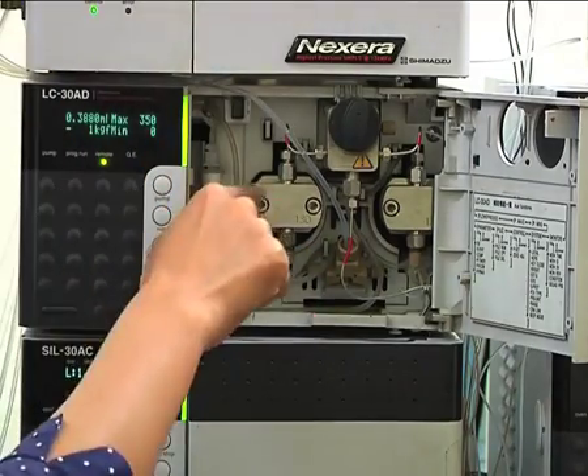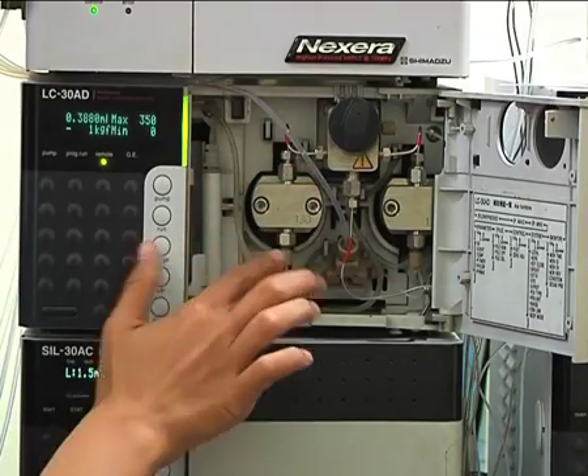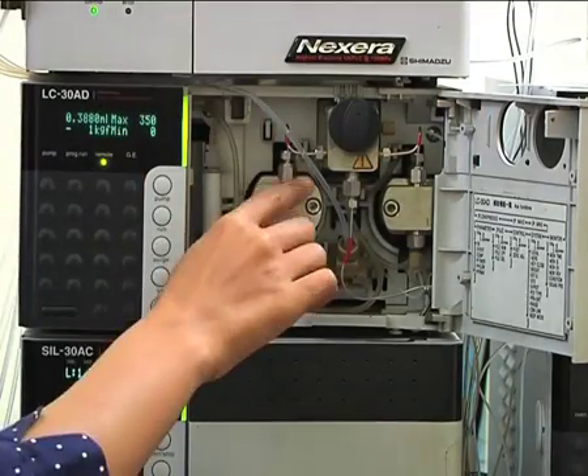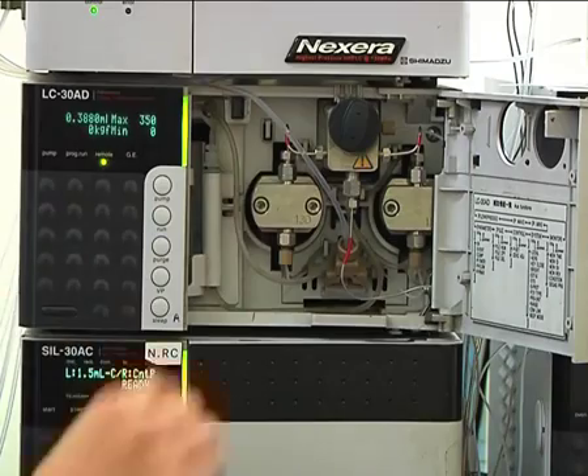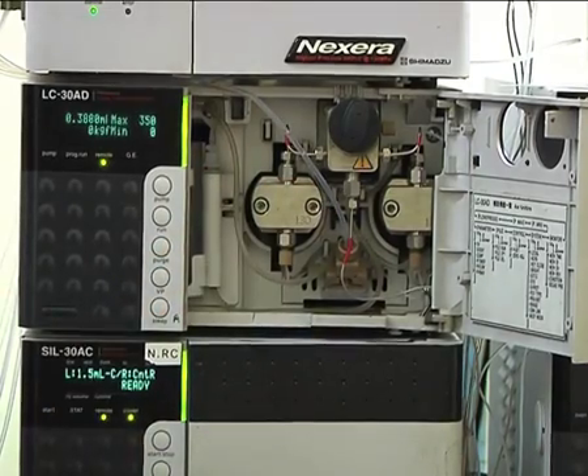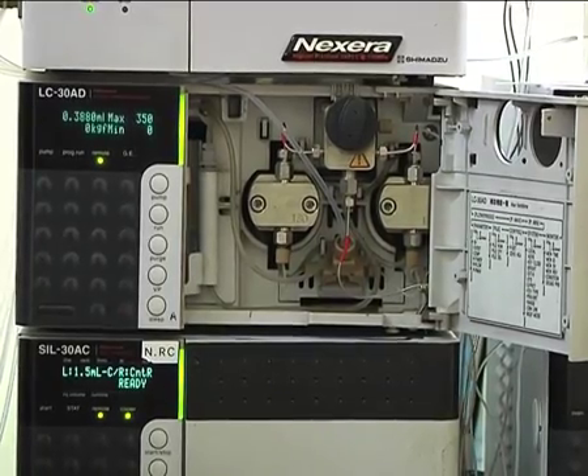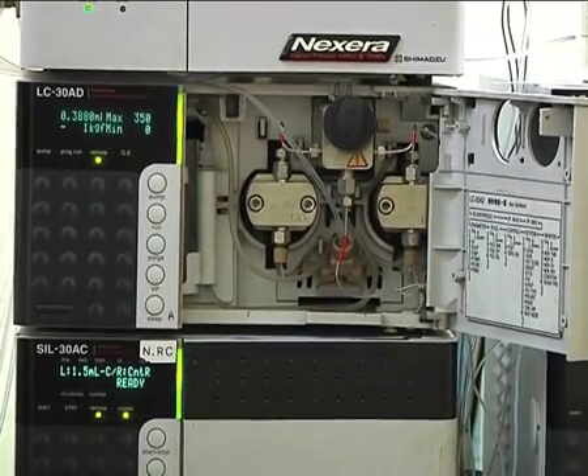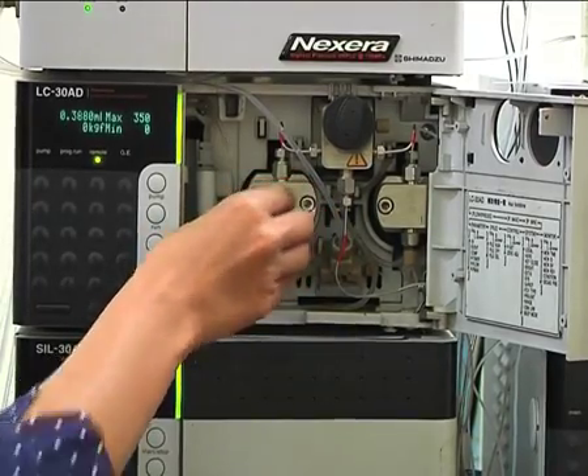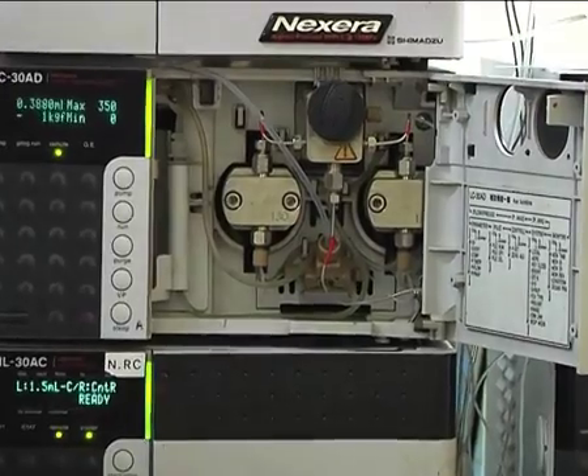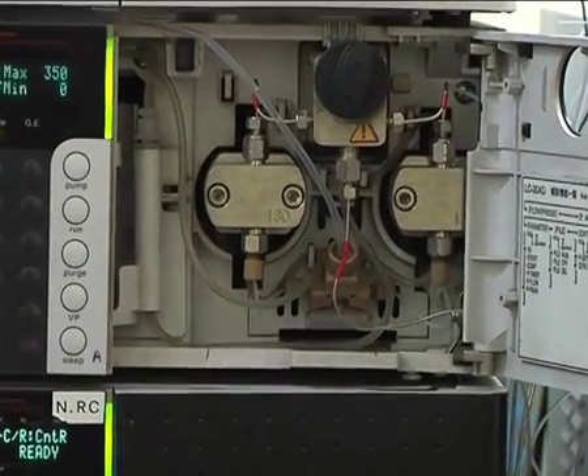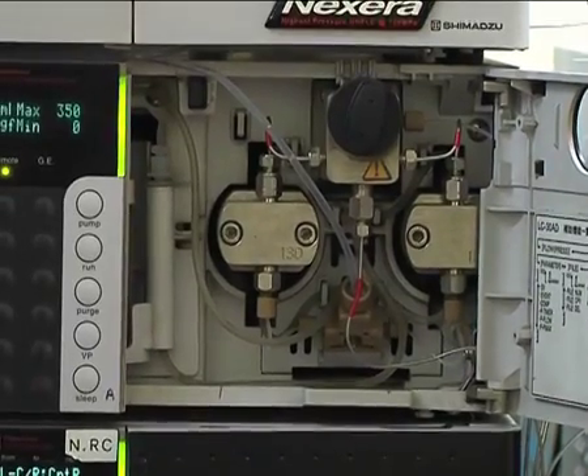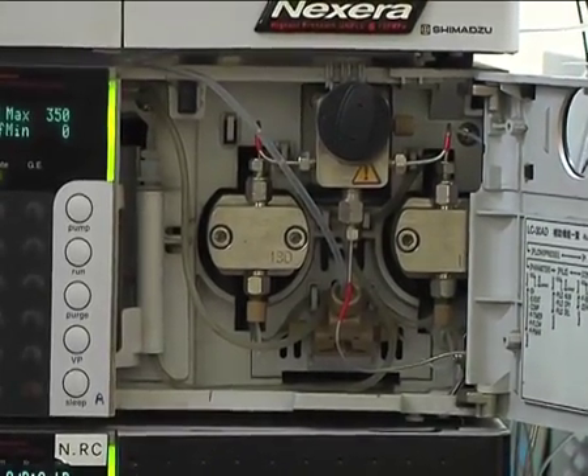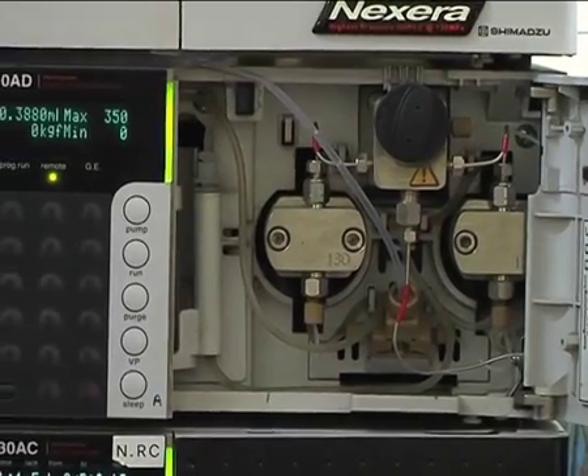Initially this valve will open, the mobile phase will fill in, then this will get closed. Now the plunger will move and pass the mobile phase to the column, and at that time this valve is open. After the mobile phase in this plunger unit is over, it has to do a refilling action. That will take hardly milliseconds because the capacity of this plunger is 10 microliter. But even for those milliseconds there is no flow on the column, and we don't want this scenario to happen. So instead of using only one reciprocating plunger, we use two plungers.